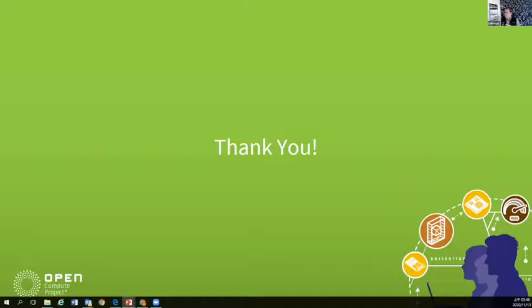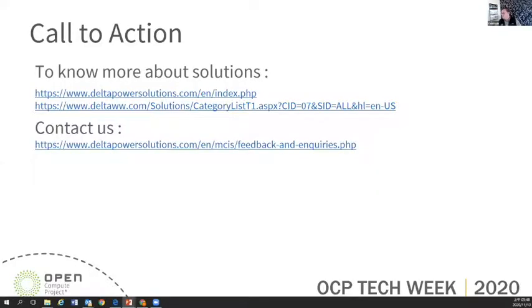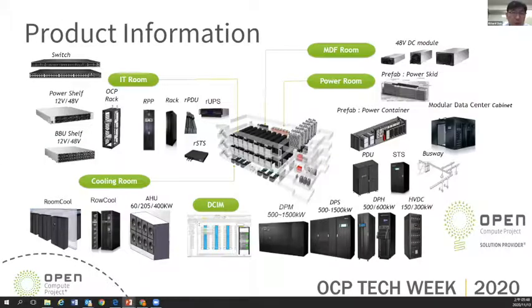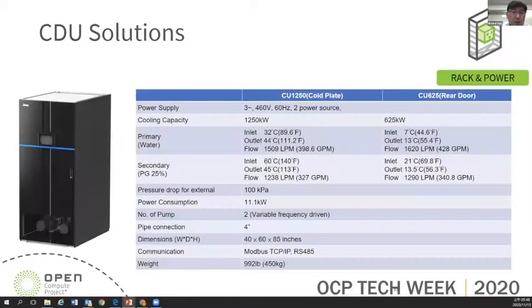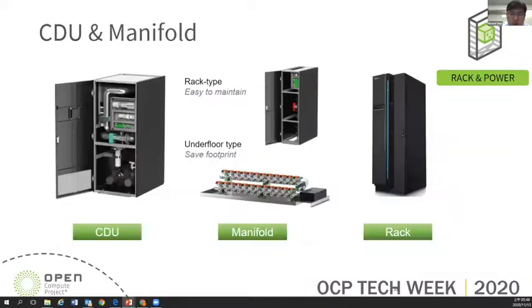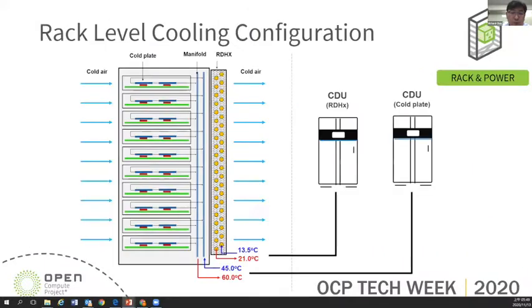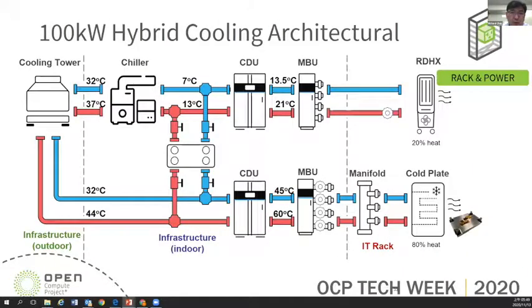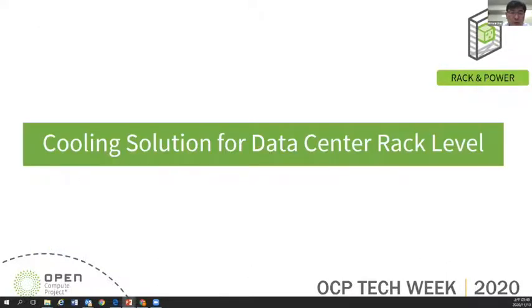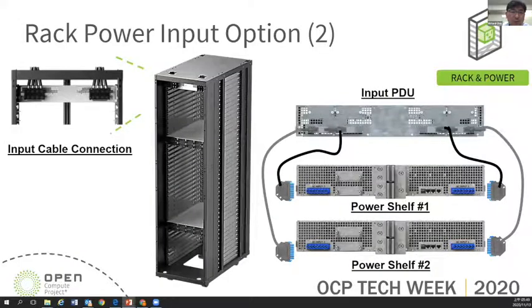Looks like there was one more question, maybe from Raul. How do you manage the amperage on the bus bars? Currently, the bus bar we use still references the V3 Open Rack. If some customers worry about the bus bar temperature, we can put a thermal sensor on the bus bar and connect it with the power shelf. The power shelf will also provide this information to the rack management. We also have a design example for the bus bar temperature measurement.